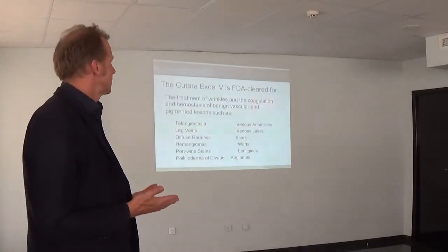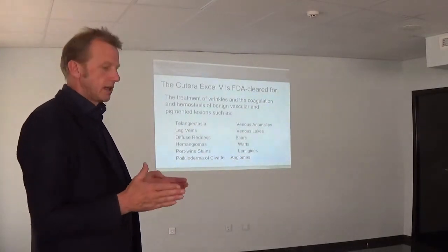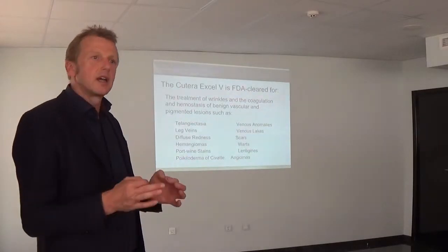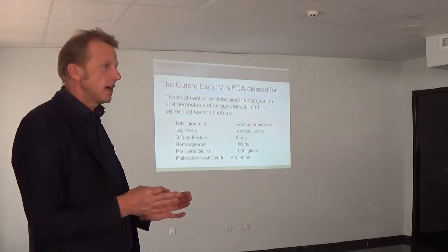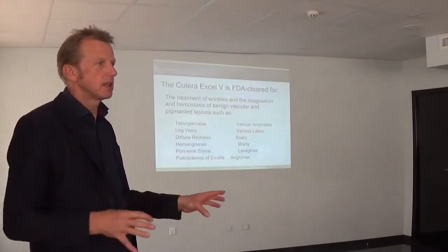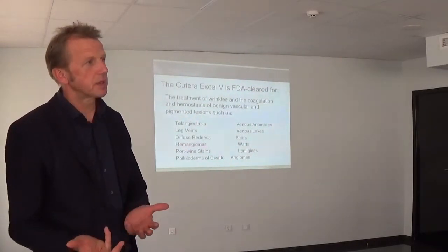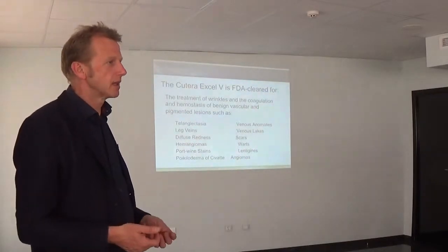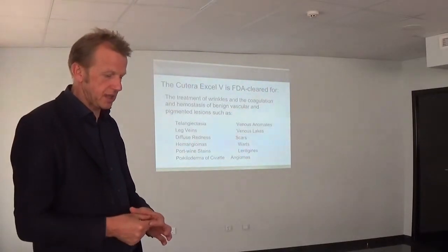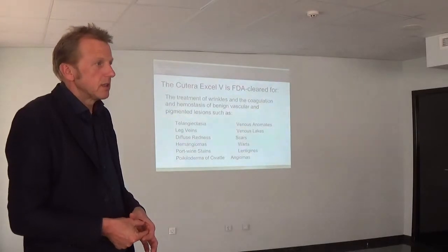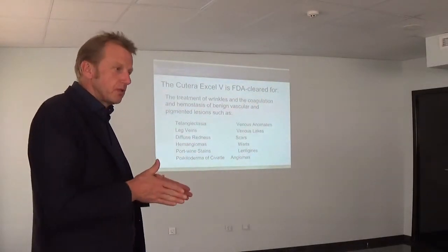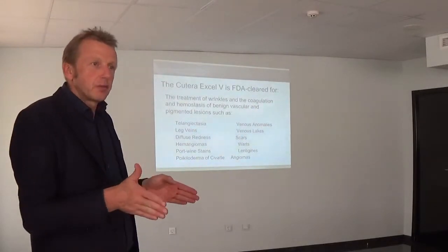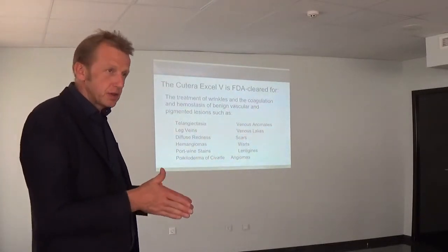The advantage of that is that we can, like Gwen says, have control over the fluence, spot size and pulse duration independently of each other, which is not possible with Limelight. With Limelight, you have a fixed spot size which is rectangular. You have a pulse duration that is variable, but it depends on the fluence.